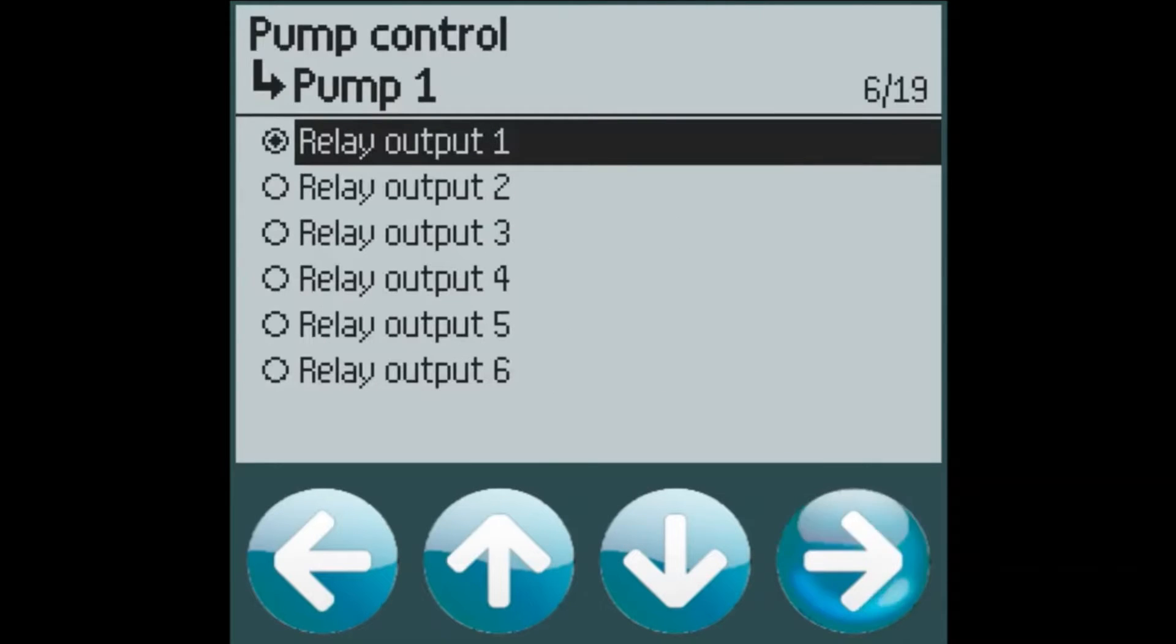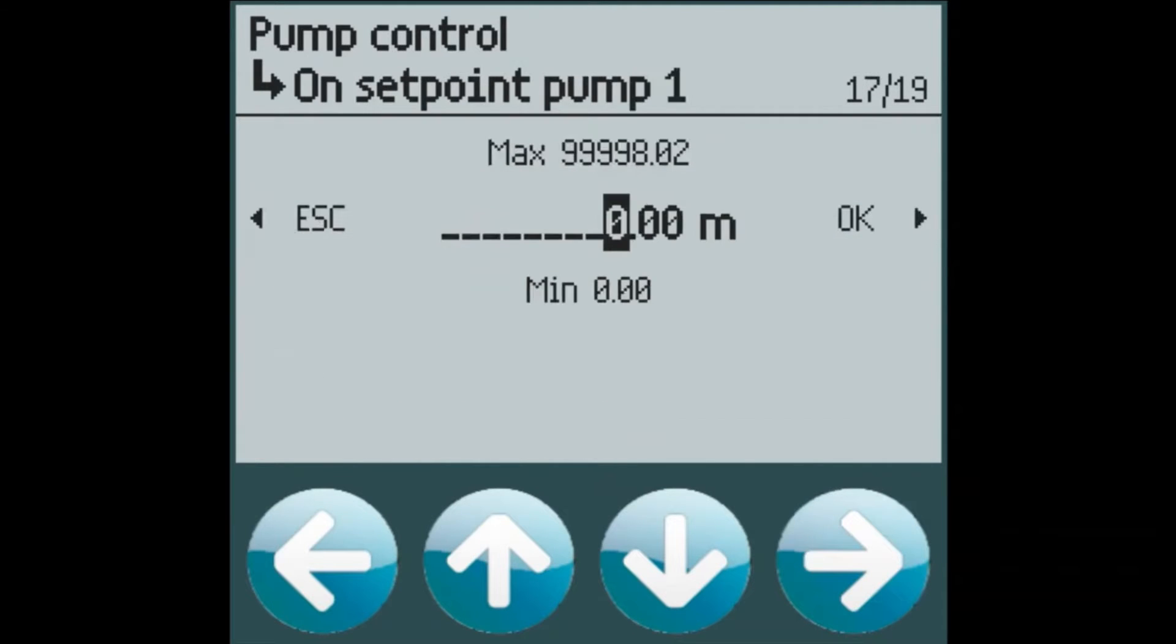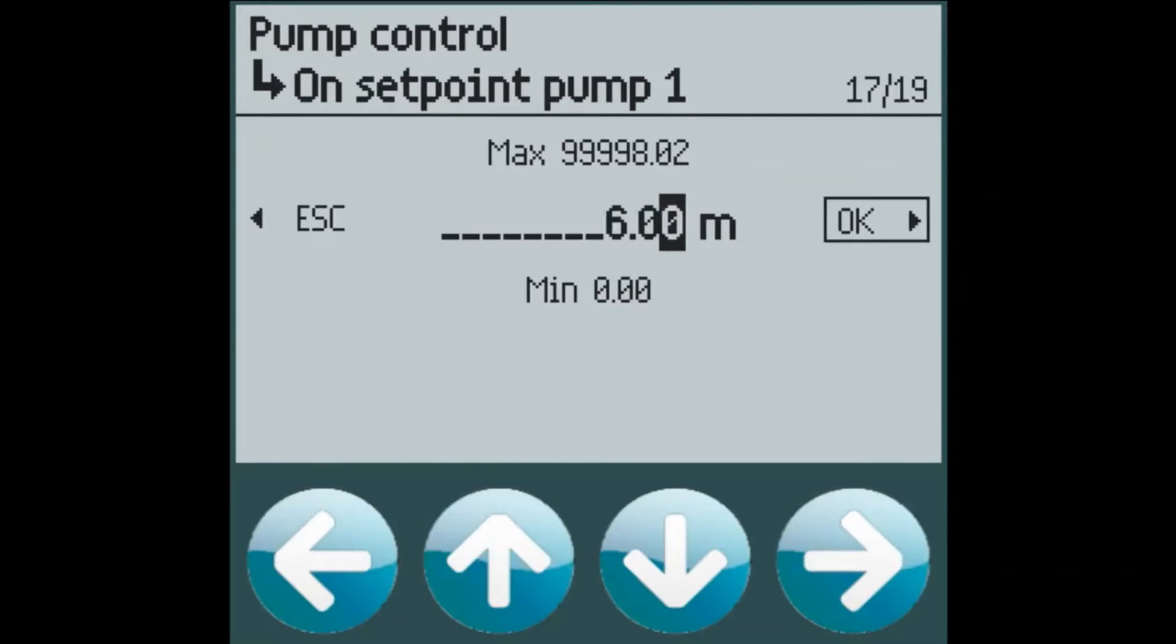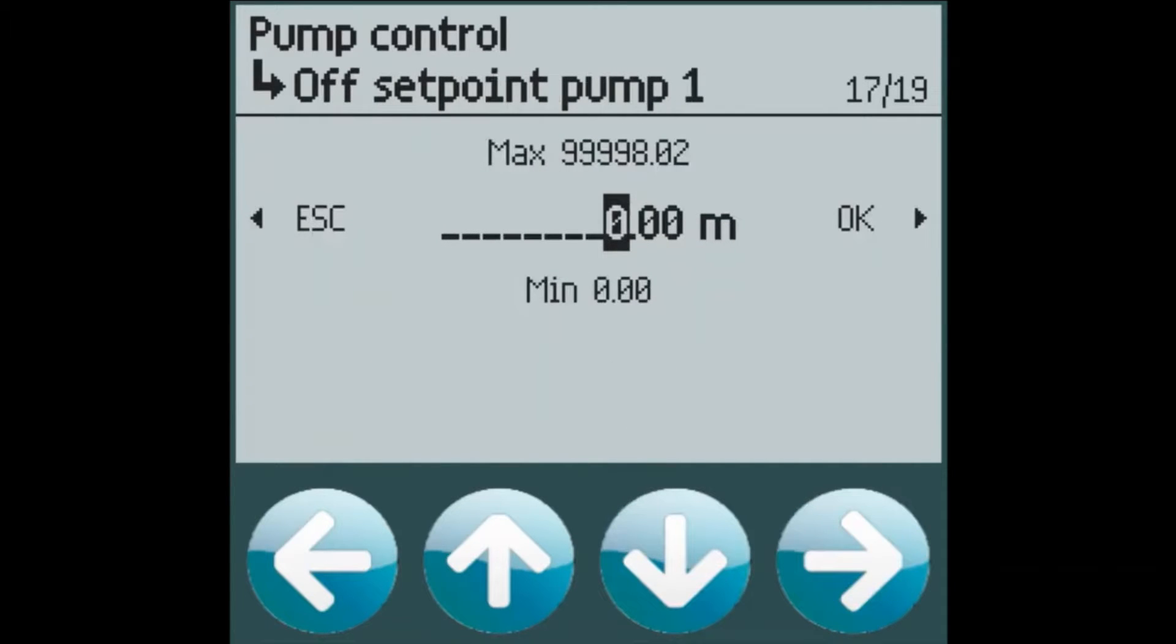Pump 1 will be on relay 1, pump 2 on relay 2, and you guessed it, pump 3 on relay 3. The on setpoint for pump 1 will be at 6 meters. And the off setpoint will be at 2 meters.